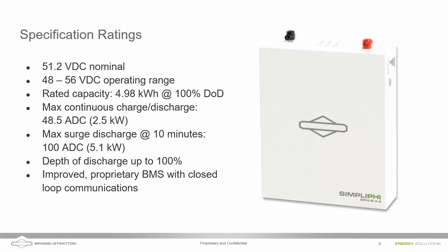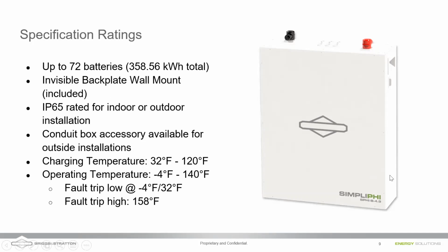The max continuous discharge is 48.5 amps DC, which is 2.5 kilowatts. And if you're discharging for a surge, maybe starting a well pump or a motor, you got 10 minutes at 5.1 kilowatts. Again, you can discharge all the way down to 0 and back up to 100 if you'd like. And there is a BMS included with closed loop communications with our inverter. Paralleling up to 72 batteries.